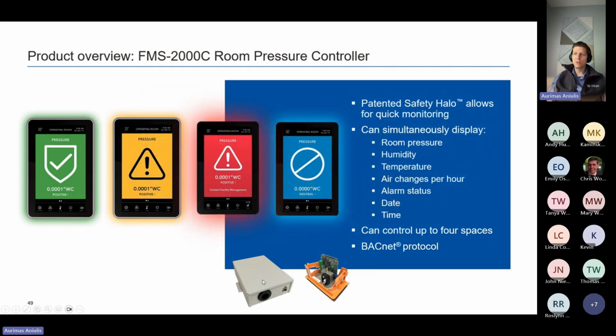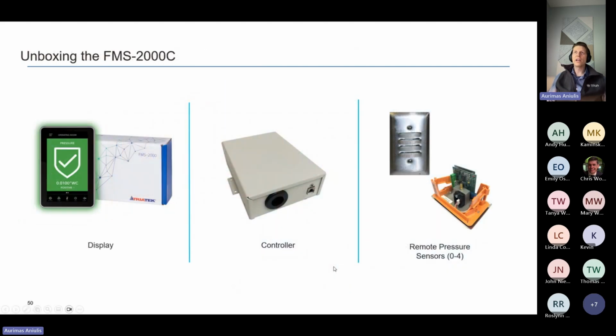Now, this is the display. You've got your controller where your wiring termination is, the CPU in this box here, and this is your room differential pressure sensor. So when you buy an FMS 2000C, this is what you're going to get. You're going to get a display, you're going to get a controller where all your wires will terminate, and you're going to have a remote pressure sensor, which we typically recommend you mount above the door facing the hallway to the entrance of the room. And the reason we do that is so that you can service it or any other equipment without having to be entering the space.